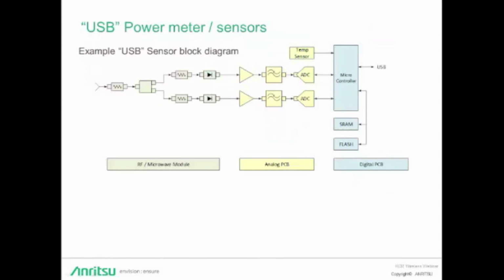Let's look at a typical architecture. You'll see here that they contain the functionality of both meter and sensor. Consider the block diagram shown here. Conceptually, it could be used to represent both a benchtop power meter and sensor system and a USB sensor. In traditional power sensors, the signal channel analog signal acquisition hardware, the preamps and the LPF, is distributed over three different components in the measuring system: the power sensor, the analog cable, and the power meter. Theoretically, this puts all three components at different ambient conditions. So the 50 megahertz reference is required to calibrate for the effects of the ambient on this analog hardware, or simply put, to calibrate the effects of the analog cable.